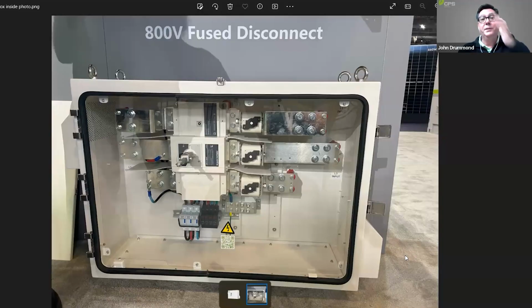And I could probably pull up some pictures and show you the inside of the switch box. So I will share my screen here and show you a little bit of the switch box. These are some pictures from when we showed this product at RE Plus in Las Vegas back in September. And this is a disconnect switch with 1,000 amp fuses and bus bars that accommodate the conductors for combining the inverters into a single output circuit. This product was UL listed to 1741. I should say listed to the UL 1741 standard with 3 275 kilowatt inverters.